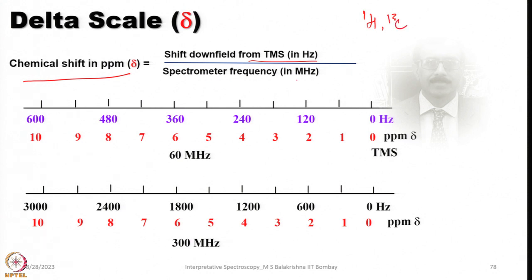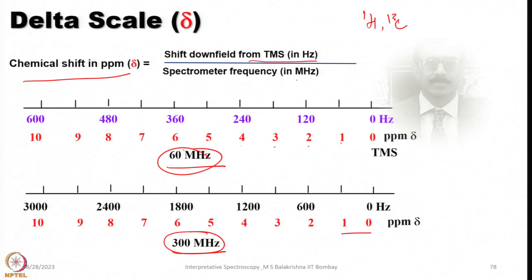The delta scale chemical shift in ppm — shift down from TMS in the case of 1H and 13C — is independent of magnetic field strength. To compare, at 60 megahertz and 300 megahertz, the chemical shift values at 1, 2, 3, 4, 5 ppm do not change — they remain steady in ppm — whereas in hertz they do change. This is the advantage and the reason chemical shifts are always given in parts per million, so that measuring at different magnetic field strengths does not matter.